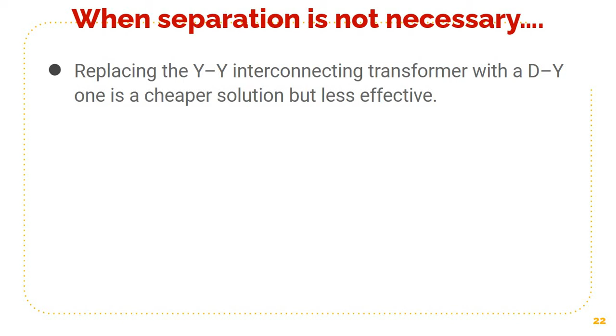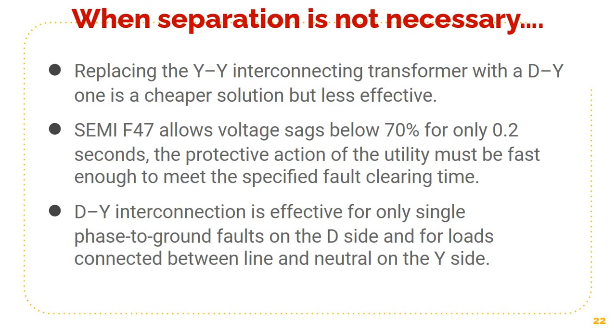Now when separation is not necessary, once again replacing the YY interconnecting transformer with DY is a cheaper solution, but is not effective. SEMI F47 allows voltage sags below 70% for only 0.2 second. So the protective devices of the utility must be fast enough to meet the specified fault clearing time. This DY interconnection is effective for only single phase to ground faults on the D side and for loads connected between line and neutral on the Y side. That is why we say that it is less effective.